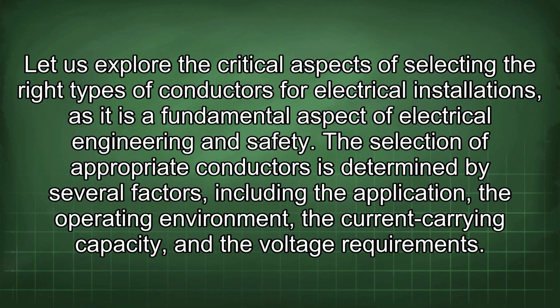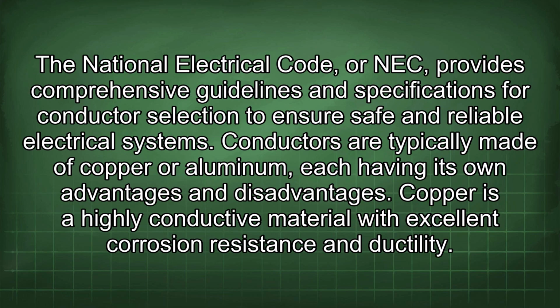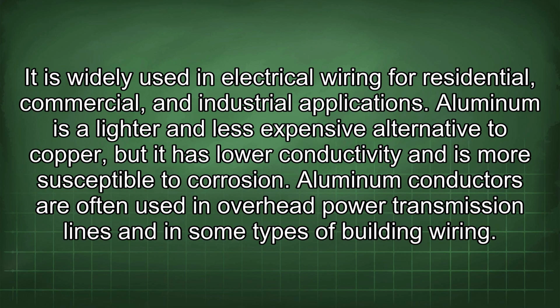The selection of appropriate conductors is determined by several factors, including the application, the operating environment, the current carrying capacity, and the voltage requirements. The National Electrical Code, or NEC, provides comprehensive guidelines and specifications for conductor selection to ensure safe and reliable electrical systems. Conductors are typically made of copper or aluminum, each having its own advantages and disadvantages. Copper is a highly conductive material with excellent corrosion resistance and ductility. It is widely used in electrical wiring for residential, commercial, and industrial applications. Aluminum is a lighter and less expensive alternative to copper, but it has lower conductivity and is more susceptible to corrosion. Aluminum conductors are often used in overhead power transmission lines and in some types of building wiring.